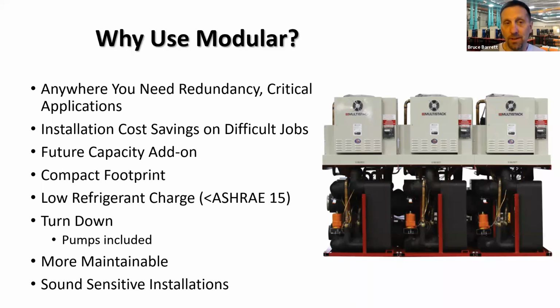Future capacity and add-on is really simple with modular chillers. Very compact footprint. We can get really creative in mechanical rooms. One of the long-standing strengths is the low refrigerant charge of most of our water-cooled equipment, less than the ASHRAE 15 requirement for ventilation in the mechanical room. So that can be big dollar savings when your equipment is in the basement or up in a penthouse. Turn down. With modular equipment, we can turn down to one heat exchanger's worth of flow, that's pump savings, or the smallest chiller's compressor's capacity. So you can have excellent turn down on the refrigeration side and excellent turn down on the water side.